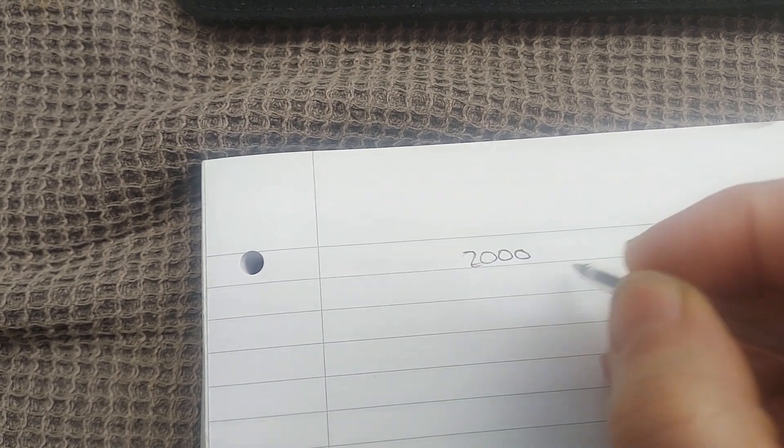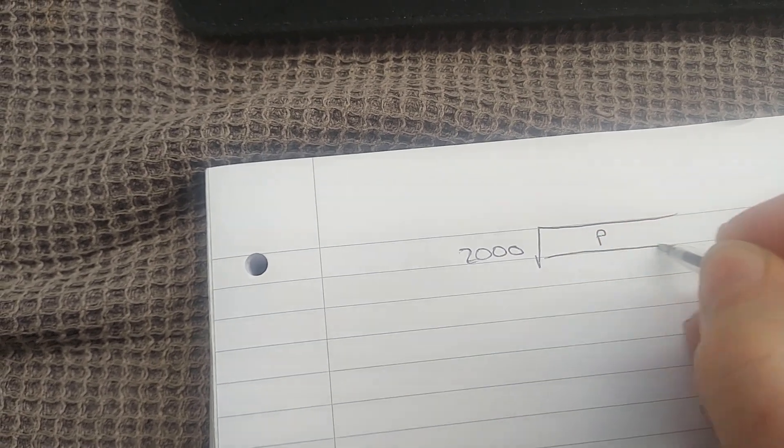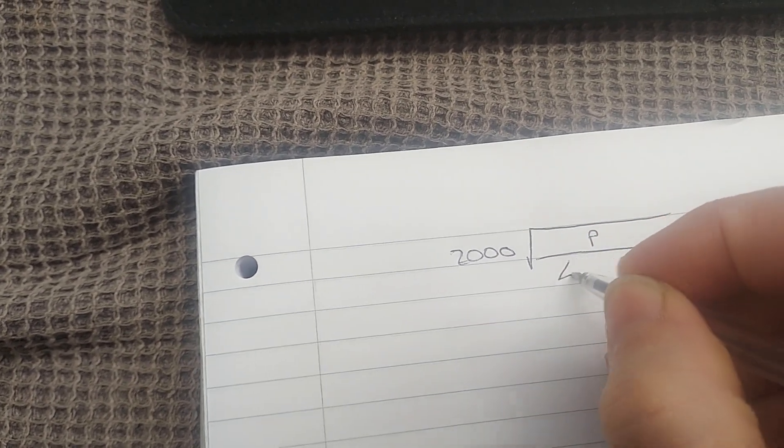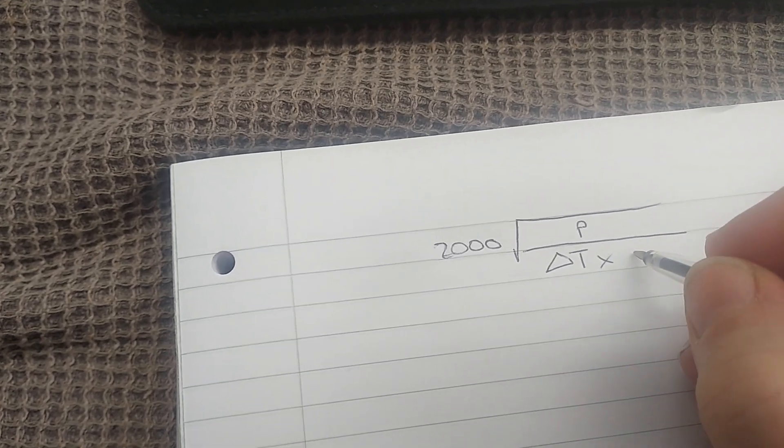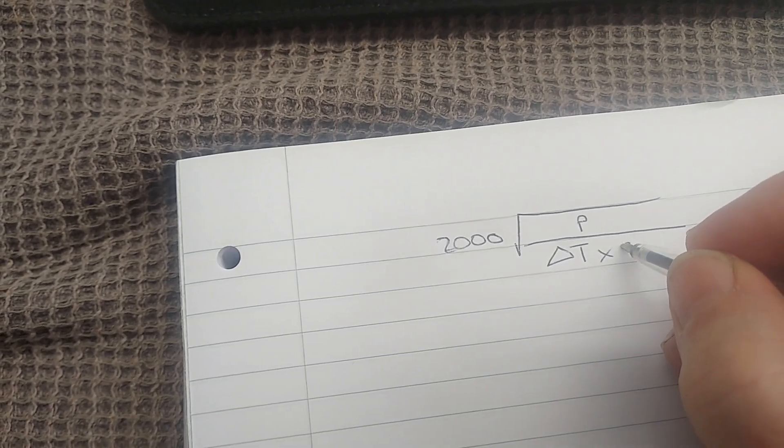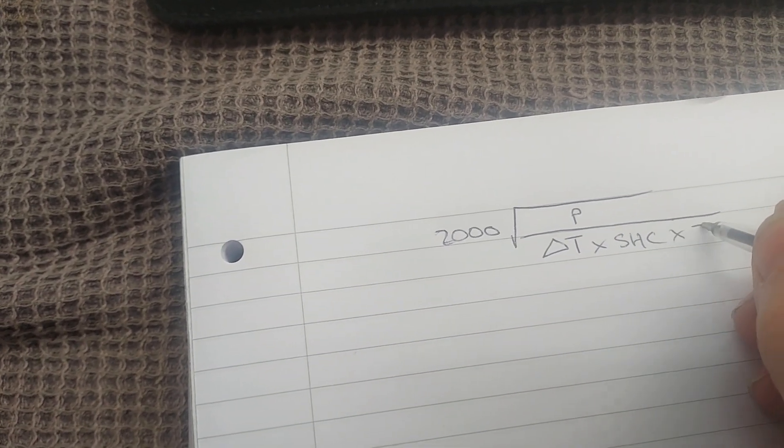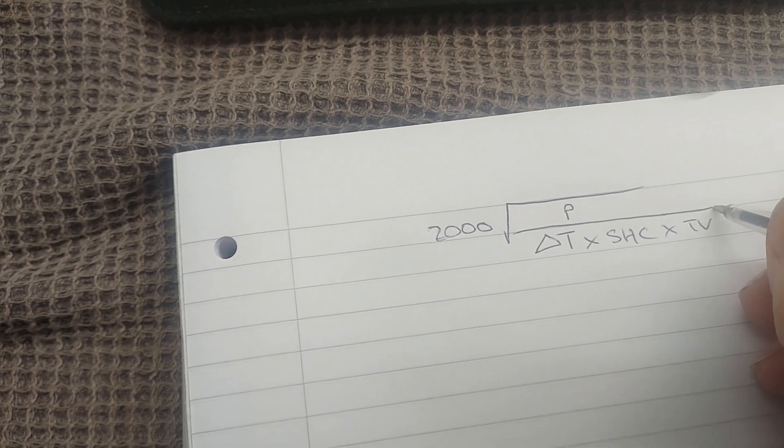I thought I'd go through those since I have a few minutes spare before I rush off to work. Let's start. Basically there is a formula that we use which is 2,000 times the square root of power over delta T times specific heat capacity times target velocity times 1,000 times pi.